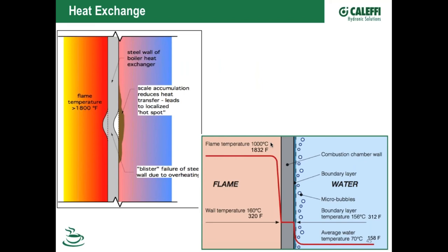This is an example of a drawing that Caleffi Italy put together showing what's going on inside a heat exchanger and a boiler. This relates to the slide Jim Paling had, with flame temperatures over 2600 degrees on some boilers. So this is your burner, your flame temperature, and this is your metal. If this is a mod-con boiler, there might be just a few thousandths of an inch of metal thickness between this high intensity flame and your fluid, whether that's water, glycol, or blend.